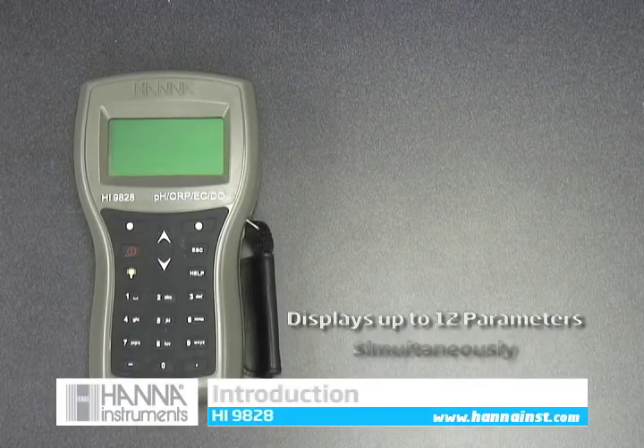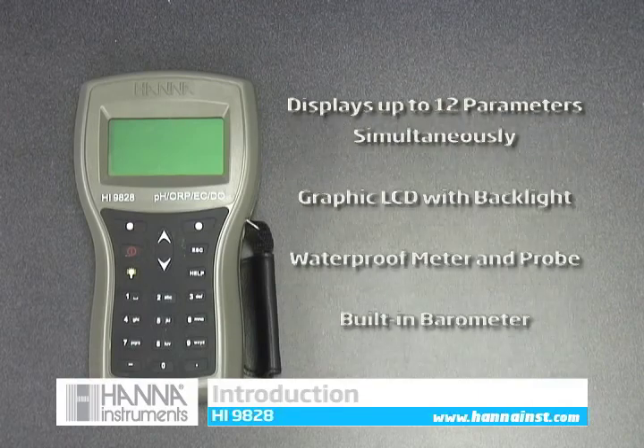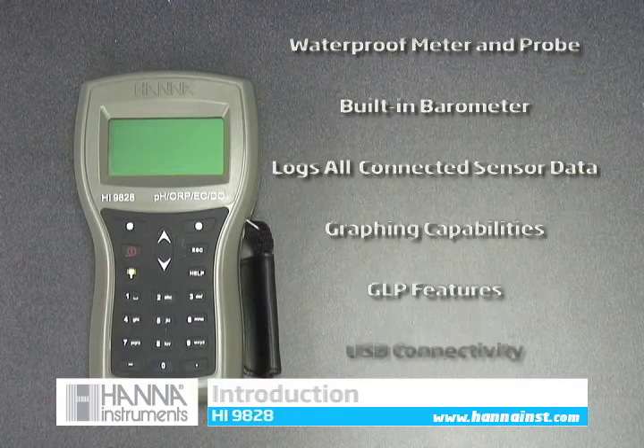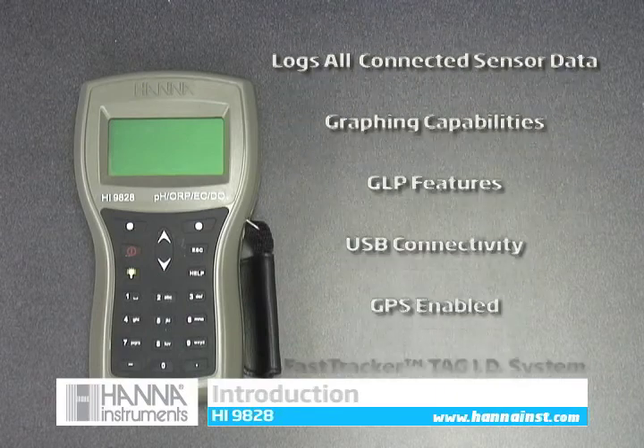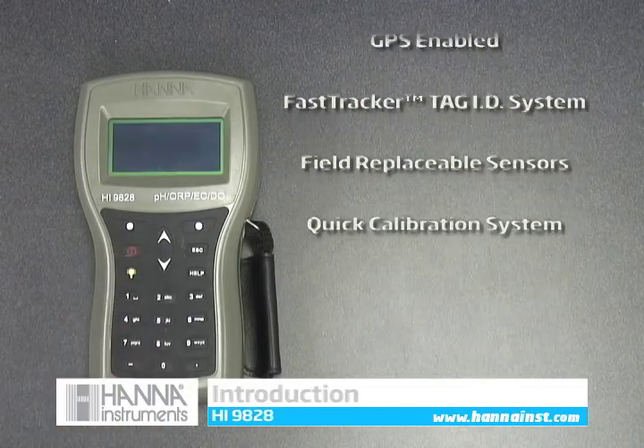This video will introduce you to the HANNA HI9828 multi-parameter meter. The waterproof HI9828 can display up to 12 parameters simultaneously on its backlit graphic LCD. The HI9828 also features GPS capabilities, field replaceable sensors, and our quick calibration system.